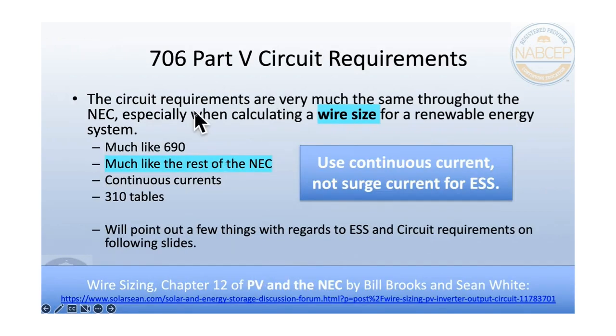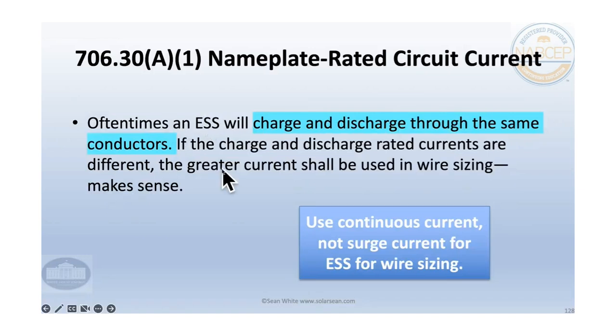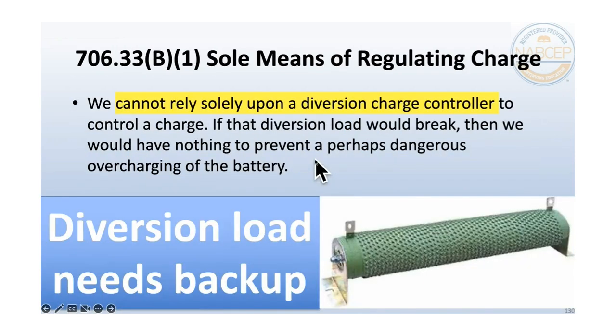Wire sizing is much like the rest of the National Electrical Code. PV and the NEC also includes energy storage. That's the book that I'm working on right now. And there's chapter 12. I posted it on the internet, and it's really complicated, but that's the correct way to do wire sizing. And that works for all the things that we're doing here. So let's see, we have the nameplate rated currents and things like that. One of the things too is we use continuous currents, not surge currents, for wire sizing and things like that. And sometimes you're going to have a greater charge current or a greater discharge current, or same with voltage, and you use the greater of whatever it is. If it takes more voltage or current to charge a battery, then you use that, of course, just obvious right there. And I just mentioned that too in the last one.